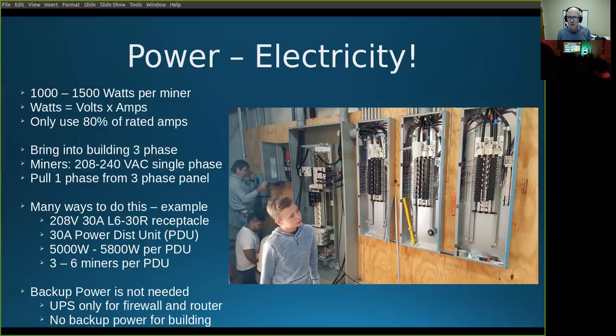So I have a bunch of 30 amp, 208 volt single phase connectors going out to some 30 amp common receptacles, like you'd plug your dryer into. Then I have a power distribution unit, which is just a big extension cord and power strip, and I can plug in, depending on the miners, 3 to 6 miners per PDU. It allows for a pretty flexible arrangement.